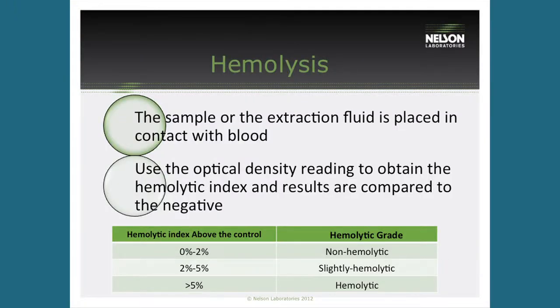We then compare the percentages of hemolysis from your negative control to your device and score them on the grade of non-hemolytic, slightly hemolytic, and hemolytic.